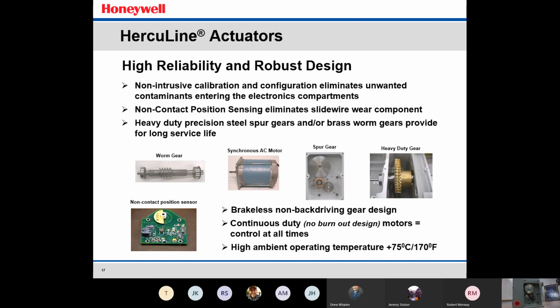Inside the actuator on the 10260, we have this heavy-duty gear that's actually a half-moon shaped gear that rides along this worm gear as it's doing its positioning. So this allows for very high accuracy and repeatability out of the actuator. Last but not least, we have the non-contact position sensor. This is the sensor that's used both in the 2000 series and the Herculine series. And as you can see, it has this half-moon shaped disc on there that will provide a voltage output based on where the actuator is in its rotation.